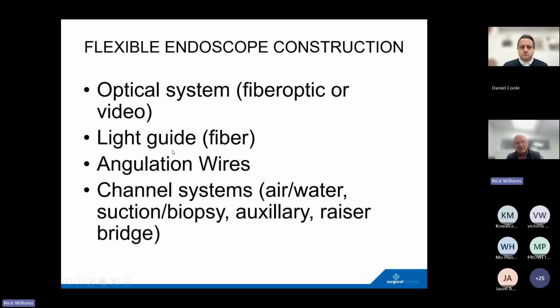And you obviously need light to get there, because you can't see anything otherwise. And usually the light guide is fiber. There are some manufacturers who use LEDs. And then you need angulation wires, because the tip of the instrument needs to be moved, usually either 2-way or 4-way, so north-south, or north-south, east-west. And then internally, depending on the priorities of the scope design, you'll need channel systems for air, water, suction and biopsy. There are some scopes that have auxiliary channels and raiser bridge channels, depending on the use of those instruments.